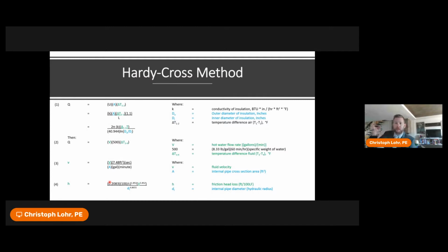So what do I mean by that? So normally plumbing systems, unlike hydronic systems, hot water return systems, domestic hot water return systems, they can be either open or closed. Hydronic systems are much easier because they're always closed and you always have 100% of the flow returning. Domestic hot water systems don't operate that way. All we're worried about is temperature maintenance. In essence, trying to get that heat source as close to the plumbing fixture as possible. So these are the 4 equations that we use, and we're utilizing these 4 equations under the assumption that the hot water return system is in a closed state. That is, none of the plumbing fixtures are open. So that way, when a fixture is open, you have that hot water demand there.